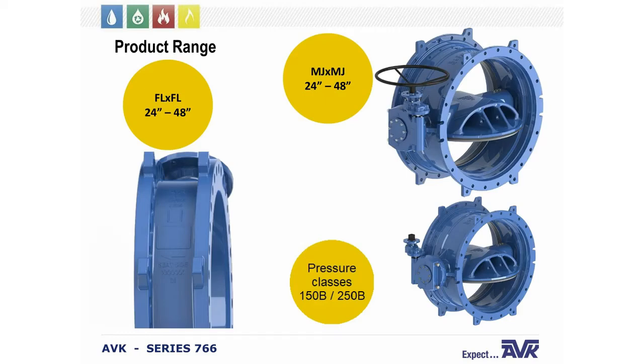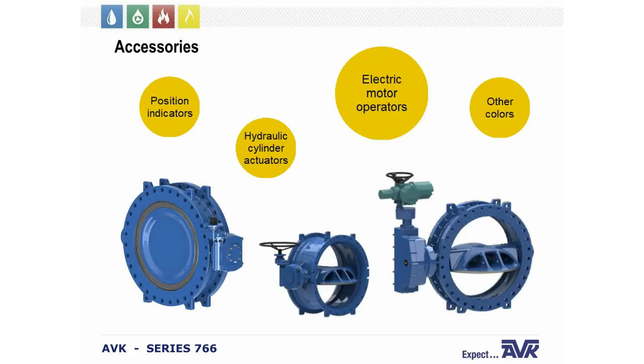The AVK Series 766 full product range is 24 inch to 48 inch. End connections through the full range are either flange by flange or MJ by MJ. The pressure classes available are 150B or 250B — the B stands for flow velocity, rated up to 16 feet per second. If you need bi-directional operation, you must request it specifically.